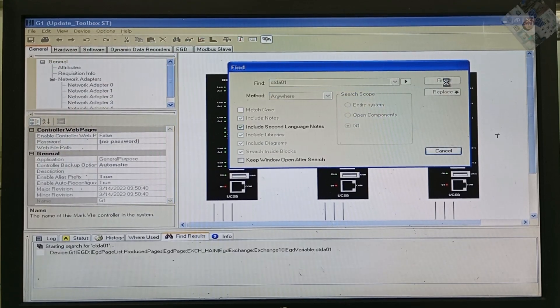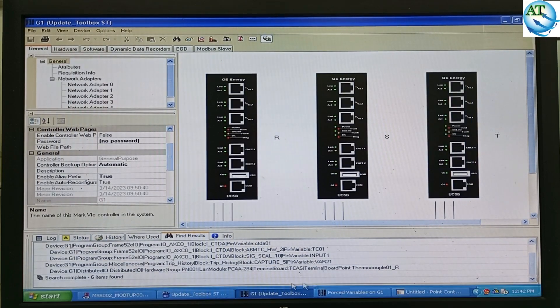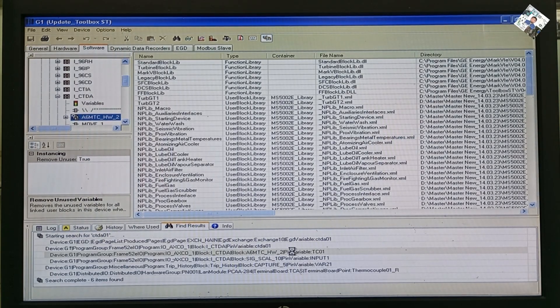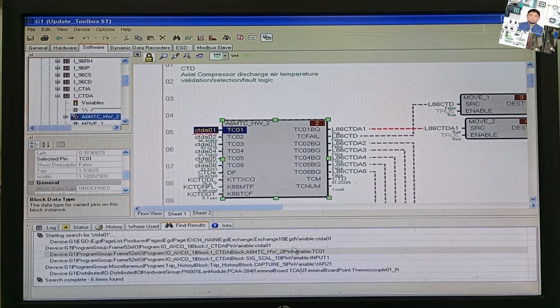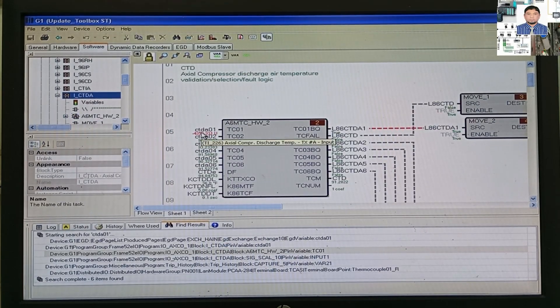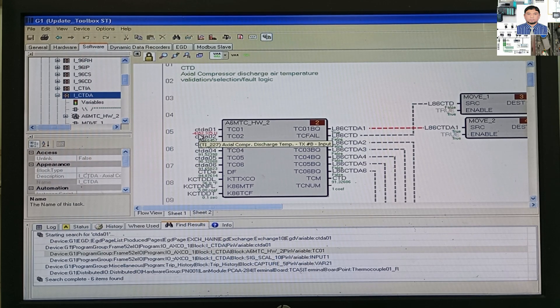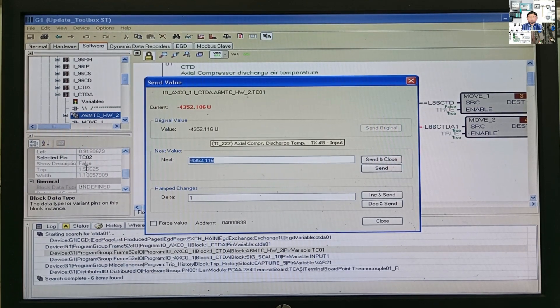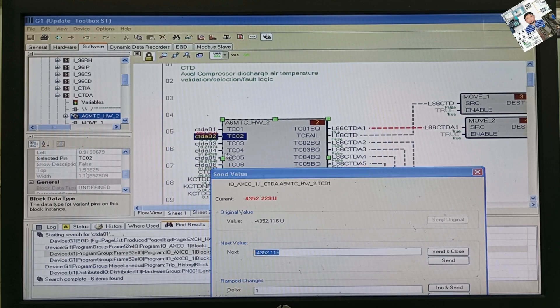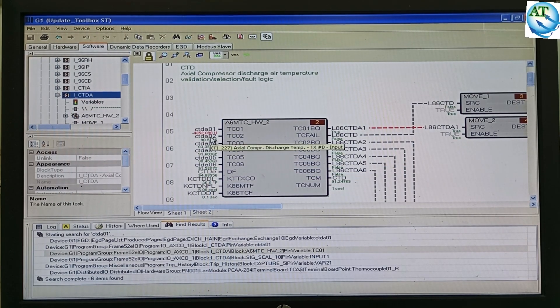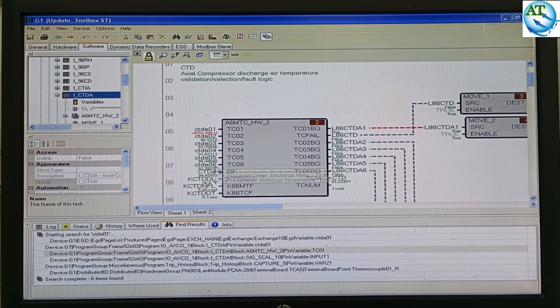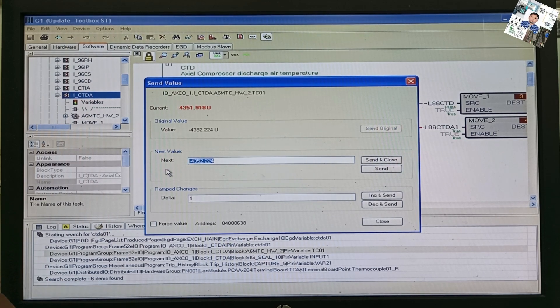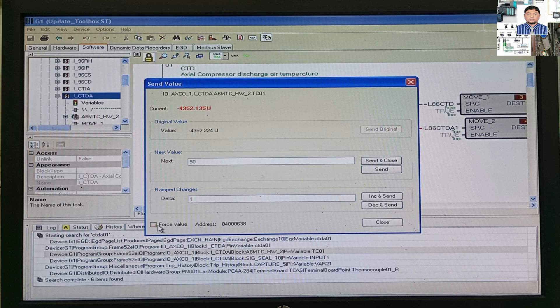Go to the Find option and write down the tag number CTDA01. Press the Find button and it will search in the logic system for the block diagram of this desired tag number. In the logic diagram, you can see the desired tag number that we want to make the force value for — for maintenance purposes, we want to change the sensor or transmitter of this temperature transmitter. We must put in a value that will not disrupt other systems or the running turbine system. Double-click on this value and put in a value. It is in degrees Fahrenheit, so we can directly replace the force value.